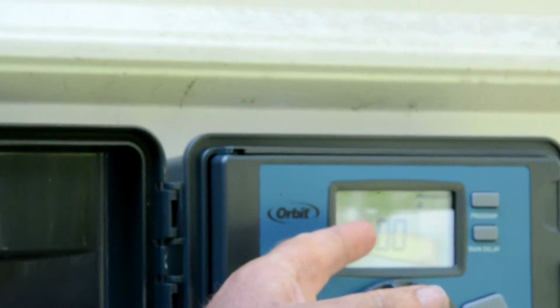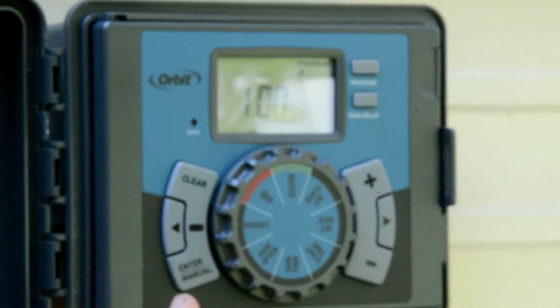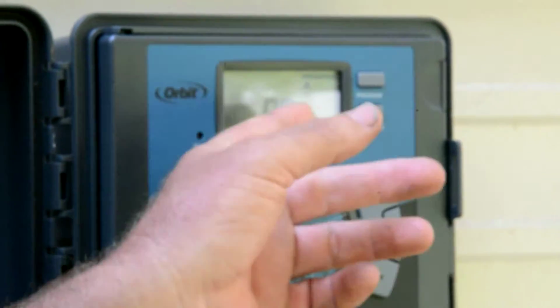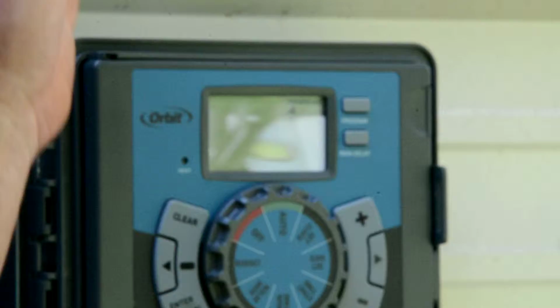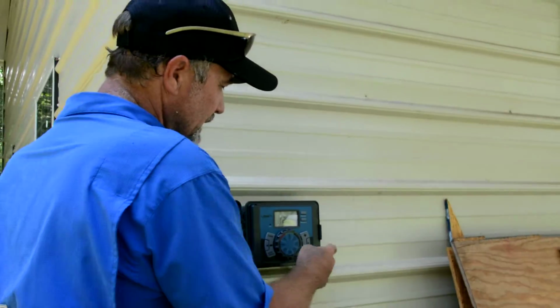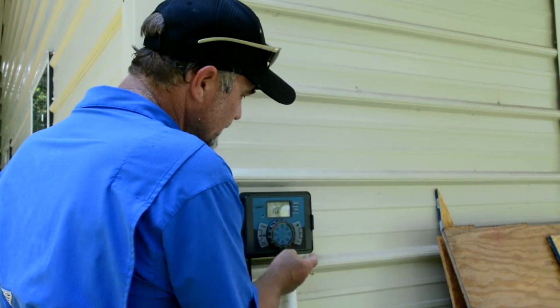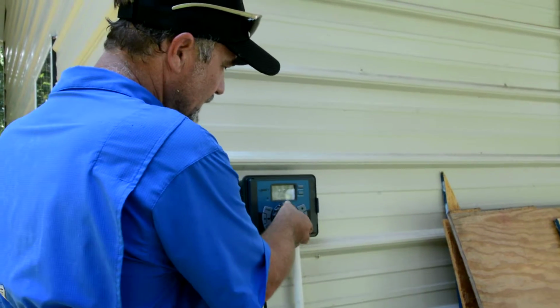the 30 minutes, 60, 60, and 60, if I wanted to quickly adjust all those run times, and let's say it's raining, it's cool, and I just don't want to water them as long, I can go down to 80%, and I have successfully taken 20% off all those run times. I haven't changed my days of the week to water. I've just watered a little bit less. Or I can go up to 120 and water 20% more. So that's the quick adjust. That's what we call the season adjust. Everything's relative to 100. Like that.